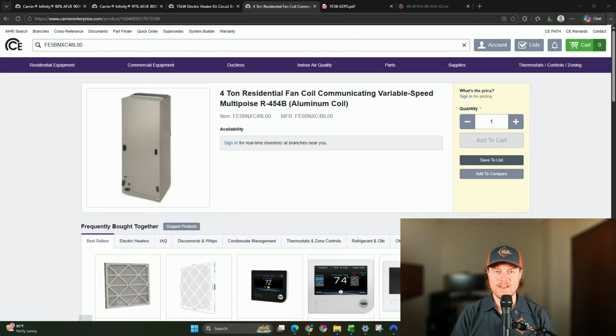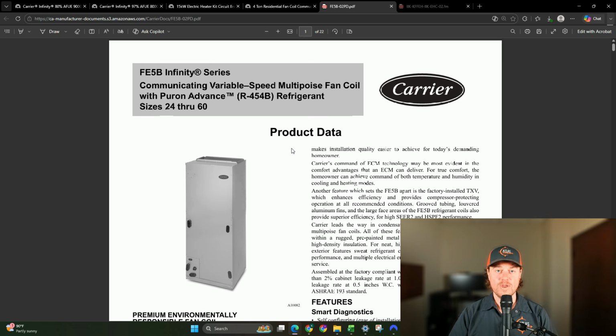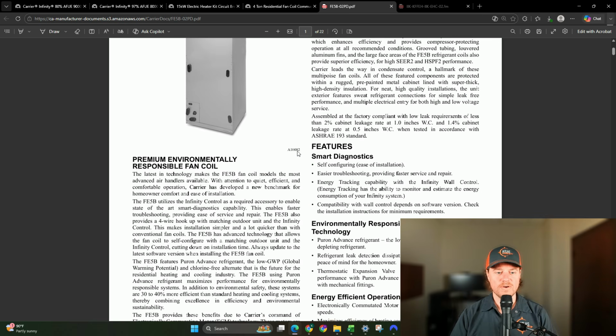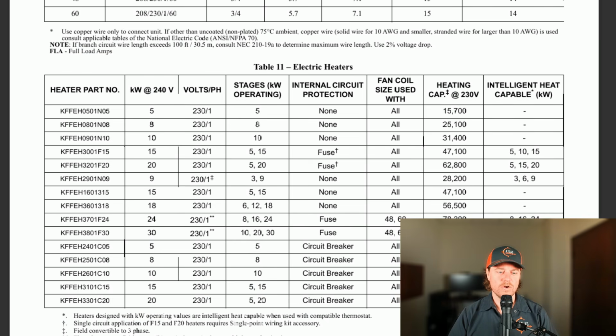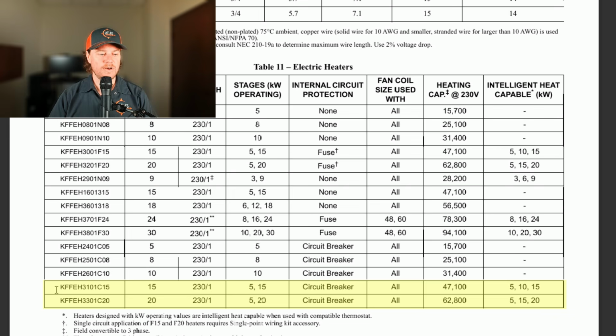Here is an Infinity air handler that we would use on a 4-ton heat pump. And when you spec the heat kit for this air handler, there's two specific ones that I look at. If we go over to the product data sheet and scroll down a ways, we come to the electric heaters that work with this unit. And if you look down here to the bottom, there's two specific ones, a 15 kW and a 20 kW. And what I like about these two, one, they have circuit breakers, and two, they can stage. For the 15 kW, you can see first stage is 5 kW, then it can ramp up to 10 kW, and then finally 15. And the 20 kW heater can go from 5 to 15 to 20.